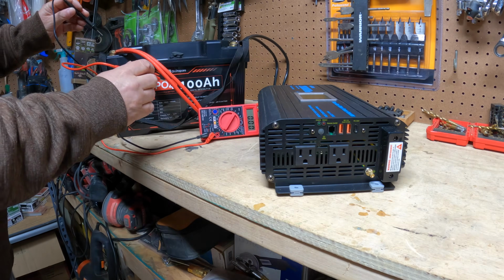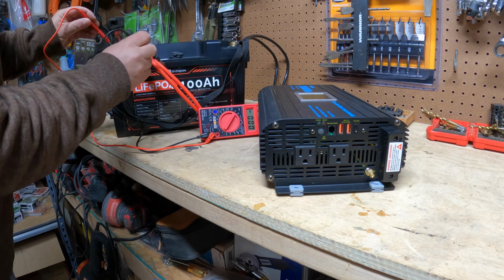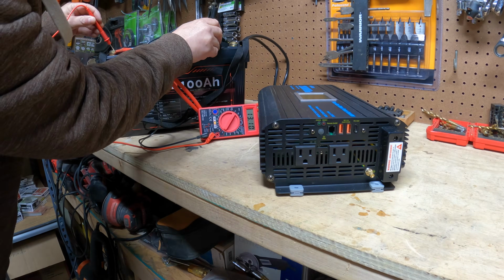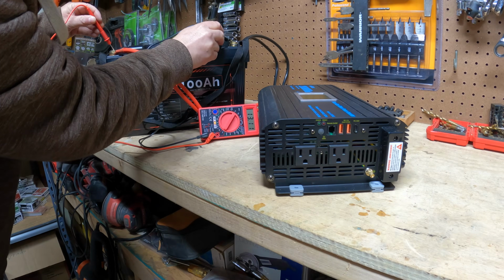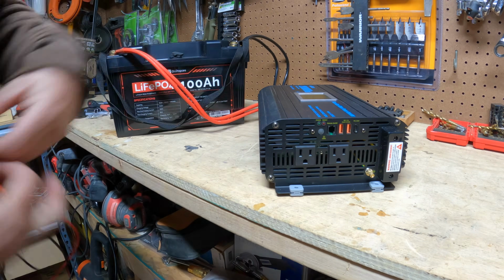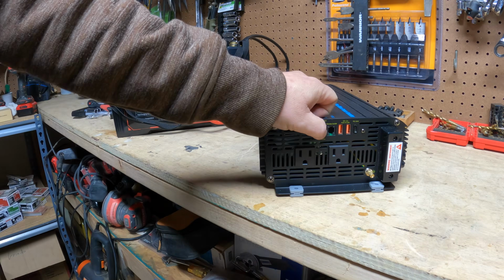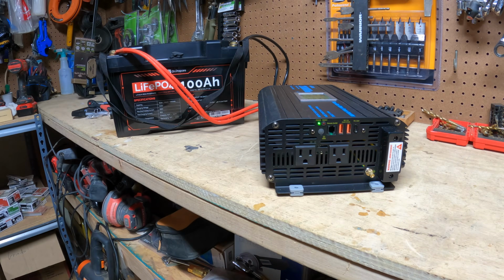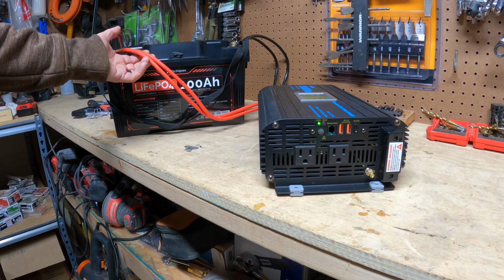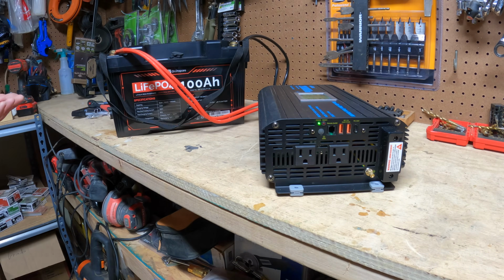So I disconnected the inverter and the battery. And now we're getting 13. So the good news is the battery is incredibly safe. When the overcurrent protection hits at over 100 amps, it shuts the battery down. The bad news is it takes about 10 minutes to get the battery back on, and I had to disconnect the inverter to get it to work.